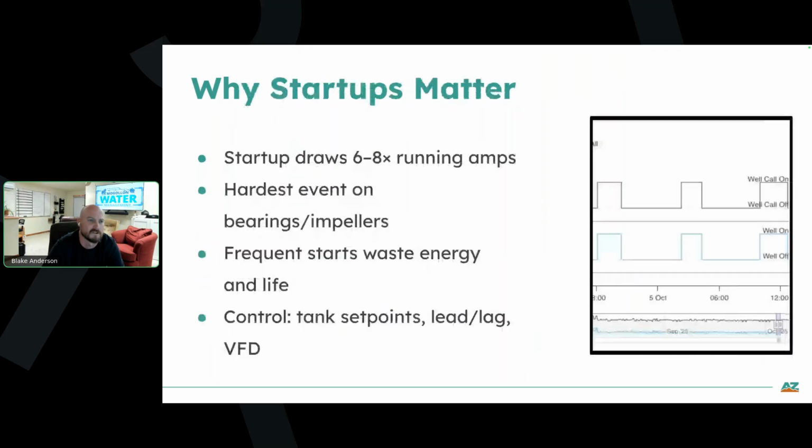And so why your startups matter. Your startups draw about 6 to 8 times the running amps your well draws once it gets running. It's your hardest event on your bearings, it's your hardest event on your impeller, and it can waste a lot of energy and life. And so you can modify these things with different control functions. You can increase the set points on your tank, so you drop an extra foot or 2 feet before it starts filling, to make this big curve rather than a bunch of short stops and starts.